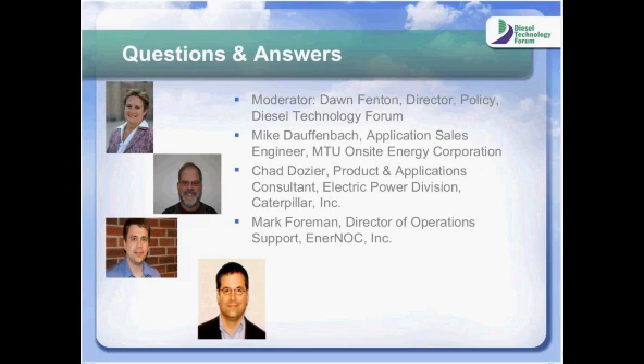The other thing I wanted to mention—if you have DF2 fuel on site for a long time, there are systems out there like clean fuel systems where they pump the fuel out of the tank, run it through filters, or put additives back in to recondition it, so you don't have to throw it away. We do this for some places with very large fuel storage tanks and low usage, particularly on some government installations.